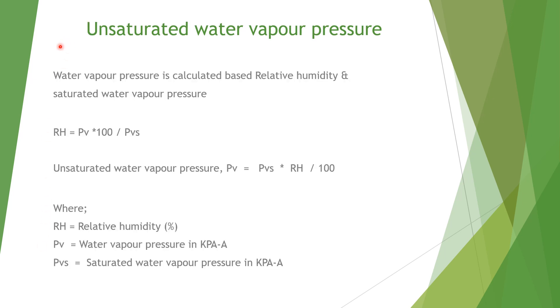Saturated water vapor pressure is only temperature-based. Unsaturated water vapor pressure is related to relative humidity. By definition, relative humidity equals the vapor pressure of water at unsaturated condition times 100 divided by saturated water vapor pressure: RH = PV × 100 / PVS. So unsaturated water vapor pressure PV equals PVS times RH divided by 100, where RH is relative humidity, PV is water vapor pressure in kiloPascal, and PVS is saturated water vapor pressure in kiloPascal absolute.